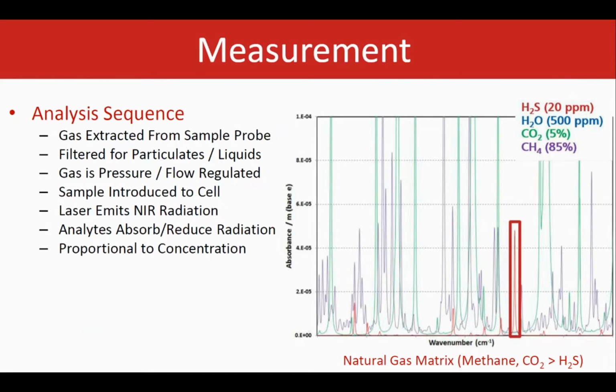The sample passes through the cell. H2S absorbs the light, and from that absorbance, the analyzer calculates the concentration of the H2S. On the graph, you can see the absorption spectra for different species, including H2S, in the background of other gases, for example, CO2 or moisture.